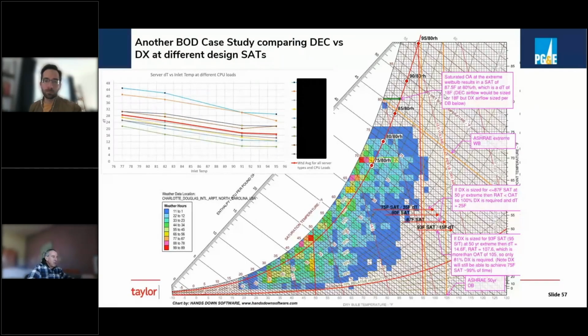I think in the end, they decided to be conservative and design it for a 75 degree supply temperature. So they had 100% cooling DX capacity. But then I think the plan was to operate it at a higher temperature as available to reduce the amount of DX and increase the amount of air economizing that they were going to be able to operate at.